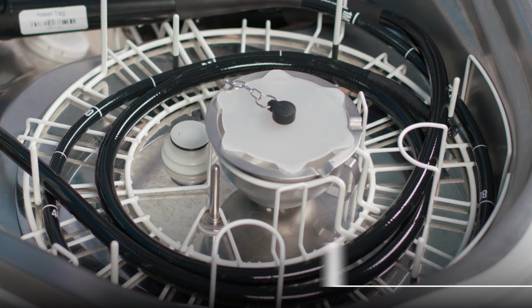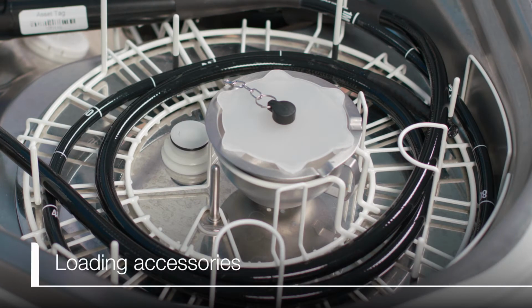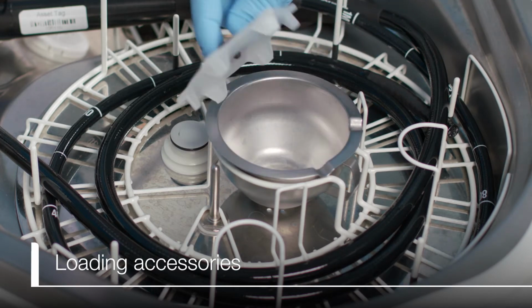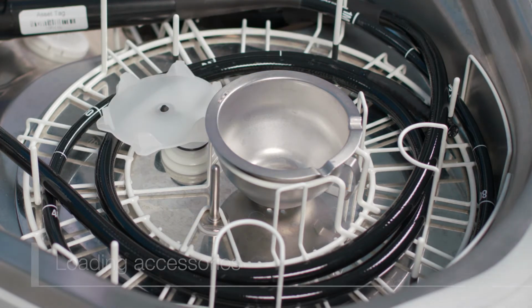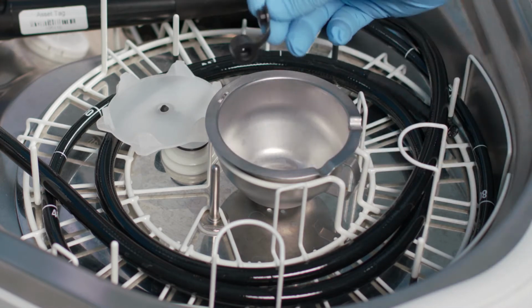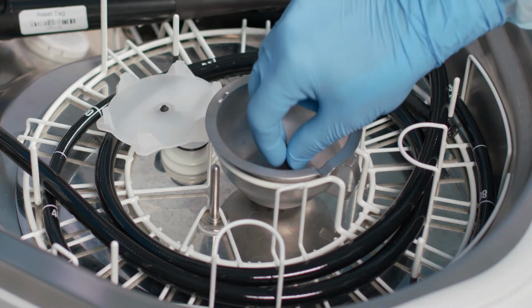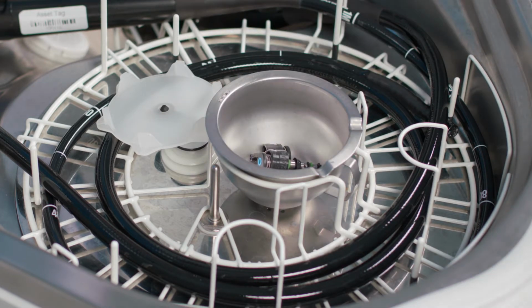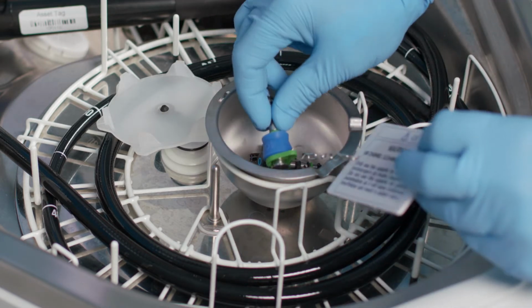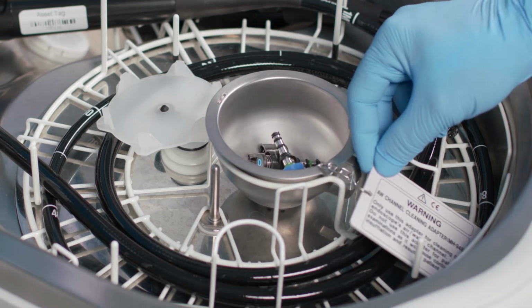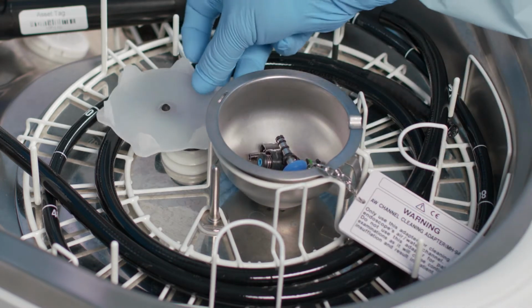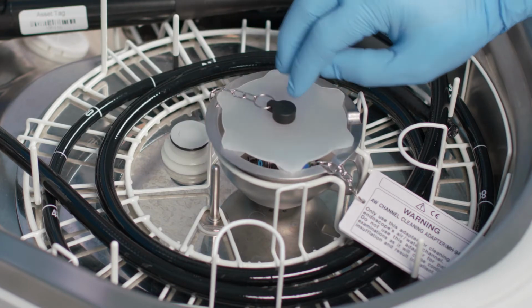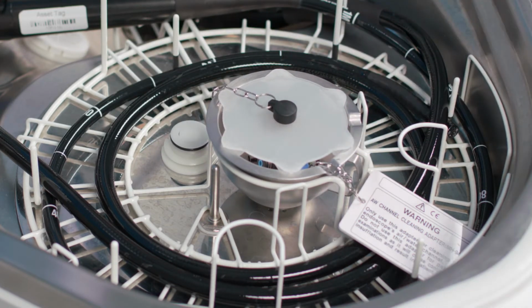Now that the endoscope is loaded into the OER-Elite basin, it's time to place the accessories into the washing case. First, remove the washing case top and place the biopsy valve in the case, followed by the other accessories. Make sure to open the biopsy valve and then disassemble the accessories when warranted. Then, set the air-water channel cleansing adapters in the washing case, ensuring that the indicator tag is draped outside of the case. Finally, close the cover of the washing case so that the chain from the air-water channel cleaning adapter is not caught in the washing case lid.